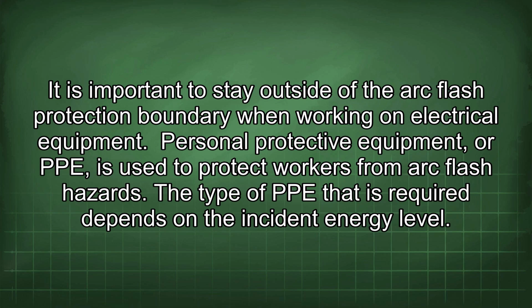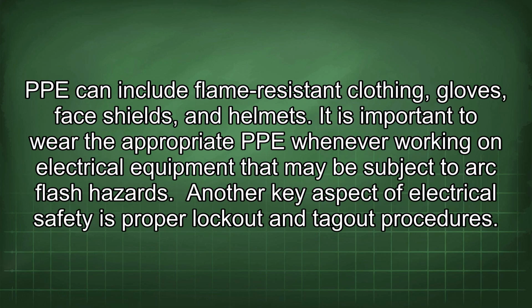Personal protective equipment, or PPE, is used to protect workers from arc flash hazards. The type of PPE that is required depends on the incident energy level. PPE can include flame-resistant clothing, gloves, face shields, and helmets. It is important to wear the appropriate PPE whenever working on electrical equipment that may be subject to arc flash hazards. Another key aspect of electrical safety is proper lockout and tagout procedures.